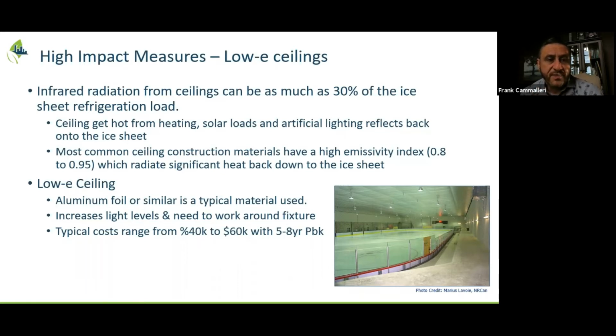Typical building materials like concrete underneath have high emissivities, between about 0.8 and 0.95, and quite a bit of that radiates back down to the ice, adding to the load, as much as 30% can be attributed to the refrigeration load.